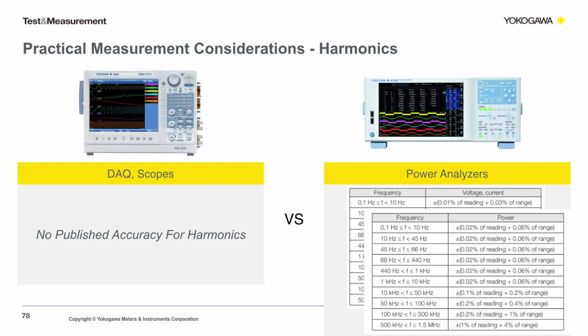So is this good or bad? Well, it depends on what you want. If you want a general idea of harmonics present in your system, accuracy specs aren't required. An FFT will suffice. If you're designing a product to comply with standards like IEEE 519, or are threatened by the power company to shut down because you're placing too much dirty power back onto the grid, you may be willing to change instruments and get a little higher level of confidence in your device with a power analyzer.